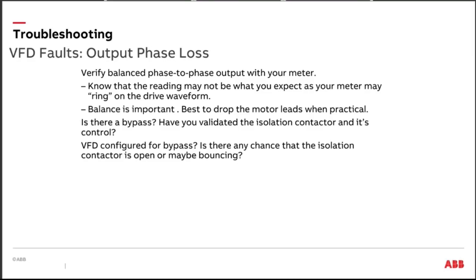I've actually seen that in a very large HVAC application at a hospital over here in Nashville, Tennessee. We had an application over there, and they had put a Hawkeye relay in and had sequenced it back into the control circuit. And this Hawkeye relay had failed, and that contactor was bouncing. It sounded like a machine gun. It was bouncing so hard and so fast. But that would have caused the drive to trip on instantaneous overcurrent. And that was a little bit of a mess for us to go in and figure out, because that Hawkeye was not on their control drawings, and we just actually had to find it inside the enclosure, okay?